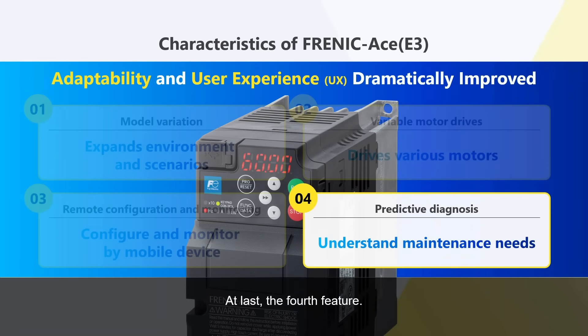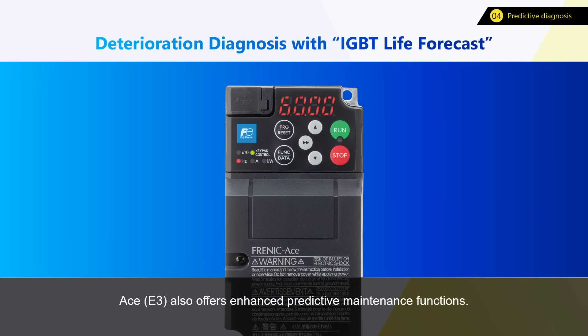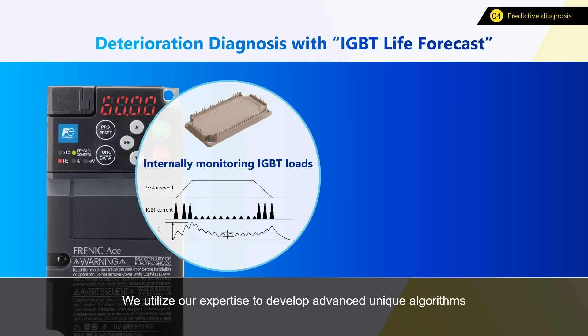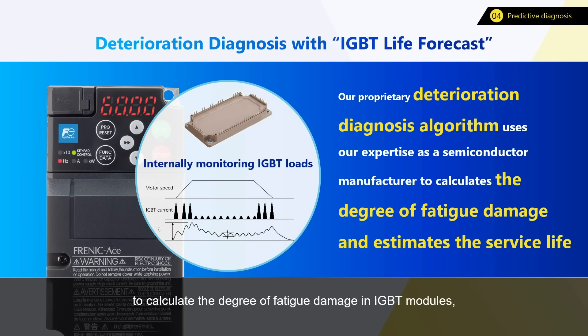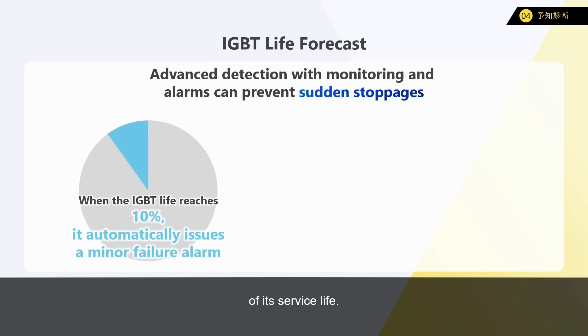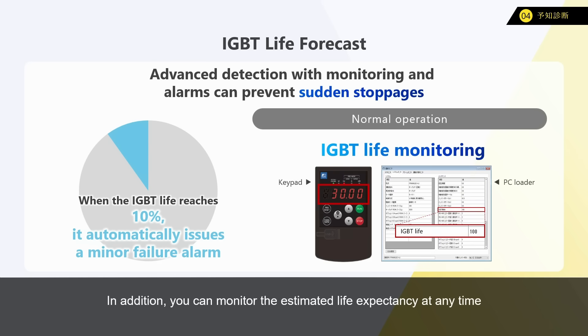At last, the fourth feature: FRENIC-Ace (E3) also offers enhanced predictive maintenance functions. Fuji Electric develops and manufactures power semiconductors as well, and we utilize our expertise to develop advanced, unique algorithms to calculate the degree of fatigue damage in IGBT modules, as they are key components in inverters. This is equipped as a life expectancy prediction function. It can be configured to issue an alarm when the IGBT reaches 10% of its service life. You can monitor the estimated life expectancy at any time on a keypad or a PC loader. By enabling advanced detection, it assists in formulating maintenance plans and prevents sudden equipment stoppages.